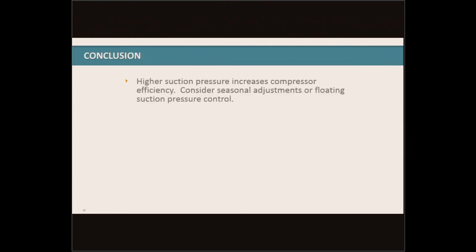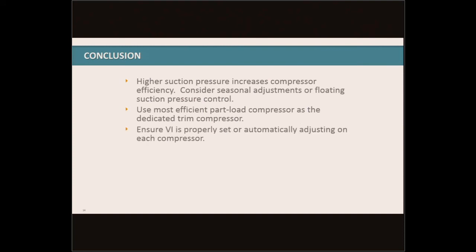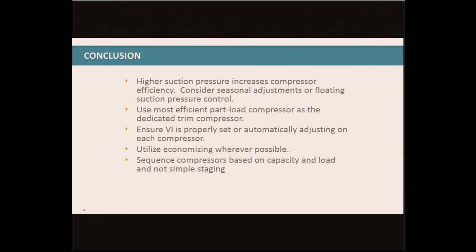In conclusion: higher suction pressure increases compressor efficiency — consider seasonal adjustments or floating suction pressure control. Use the most efficient part load compressor as a dedicated trim compressor. Ensure your VI is properly set or automatically adjusting on each compressor. Utilize economizing whenever possible. And sequence compressors based on capacity and load, not just simple staging. I hope you found this useful. Thank you very much.